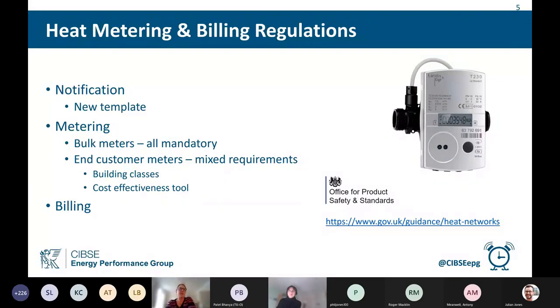Heat network suppliers will need to determine which building class each of the buildings on their network falls into, and this will determine whether or not a meter needs to be installed. The three classes are viable, exempt, and open. Viable means you have to put one in, and that's mostly new build. Exempt is where you don't have to, and that covers some existing buildings like supported housing or almshouse accommodation, that kind of thing. And then the biggest class, which is the most challenging, is the open class, which would be the majority of existing buildings.